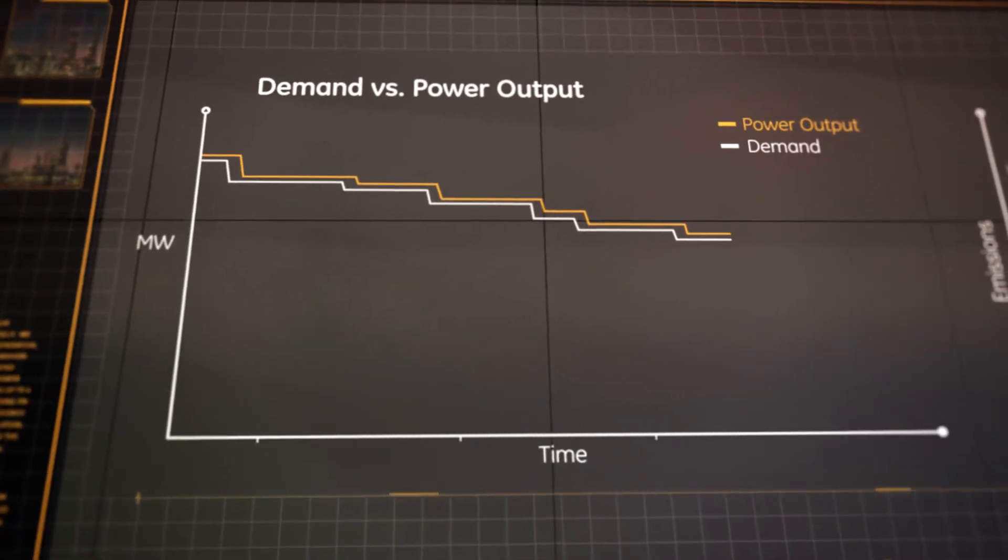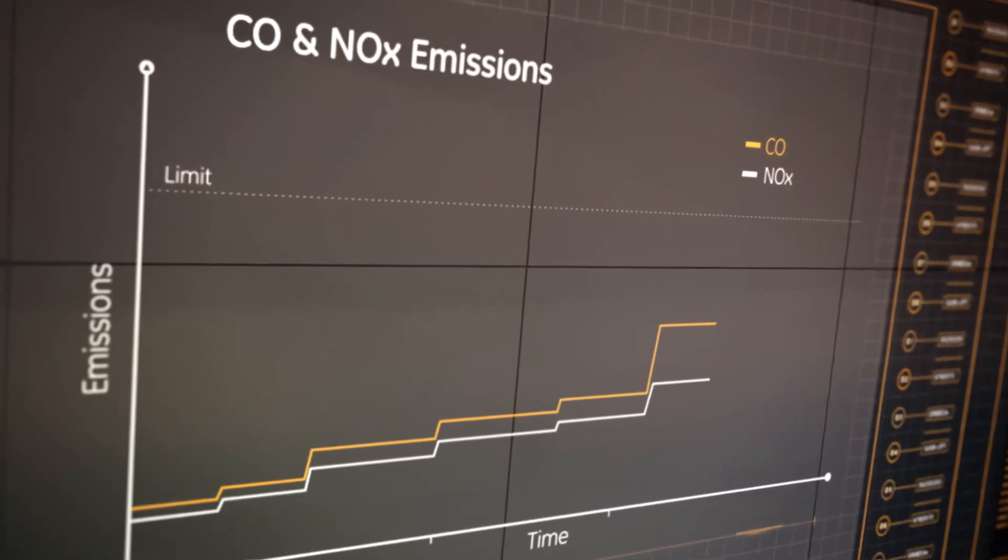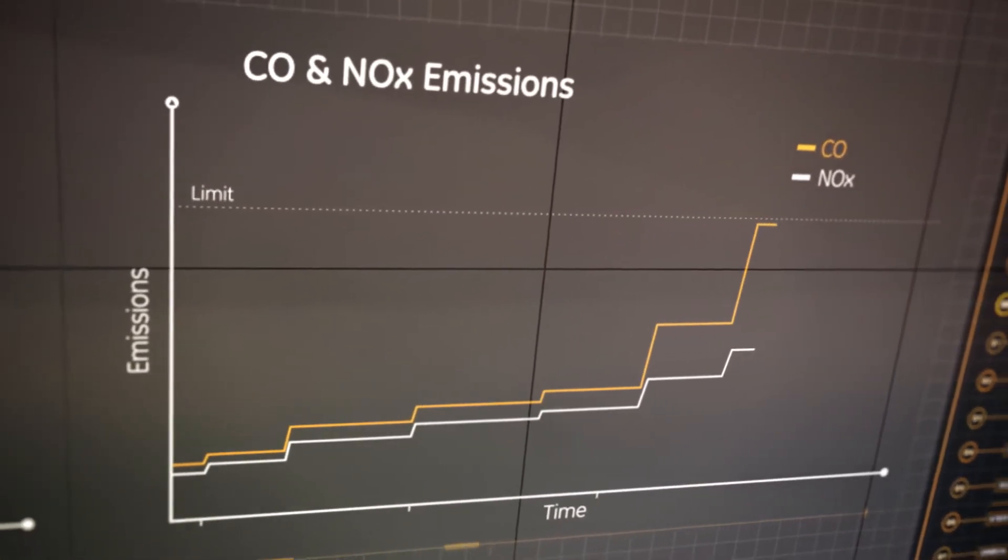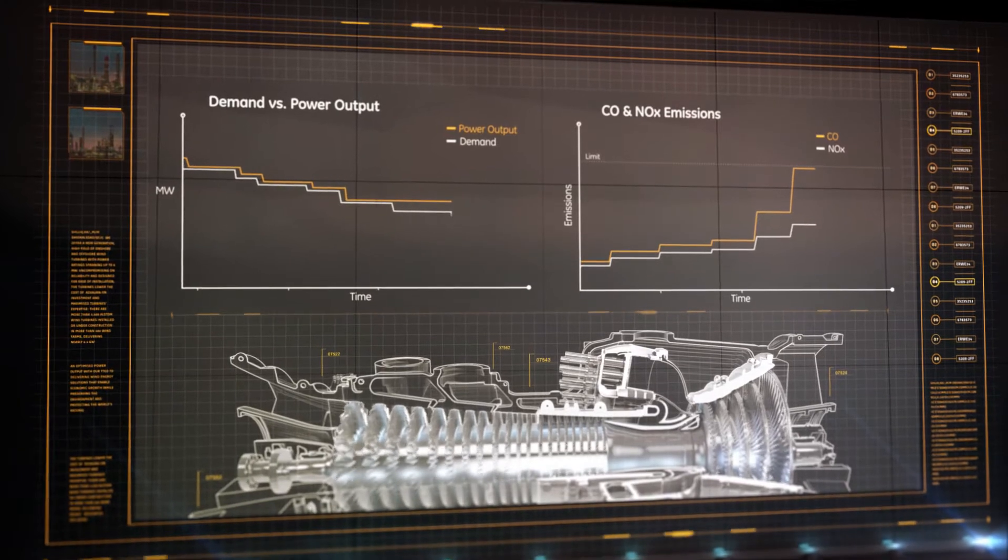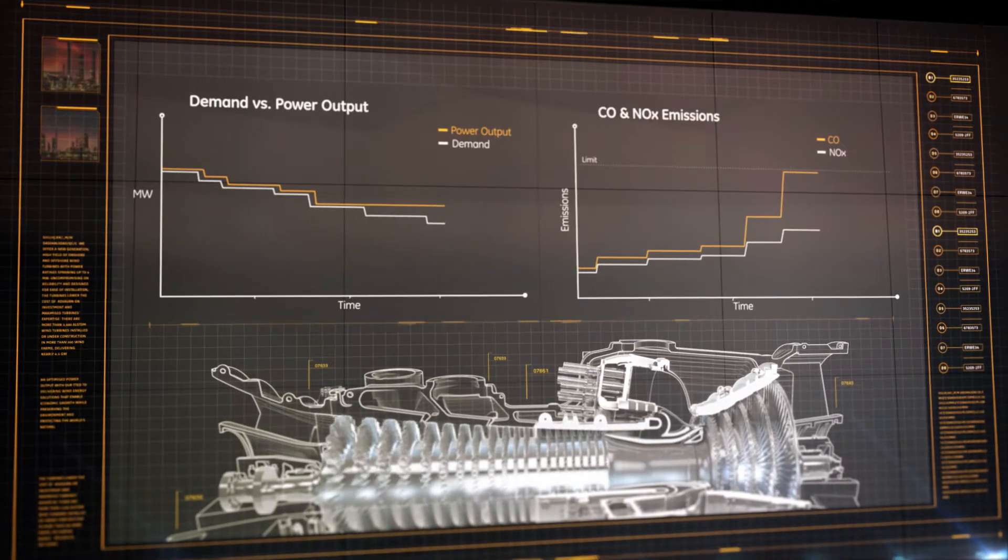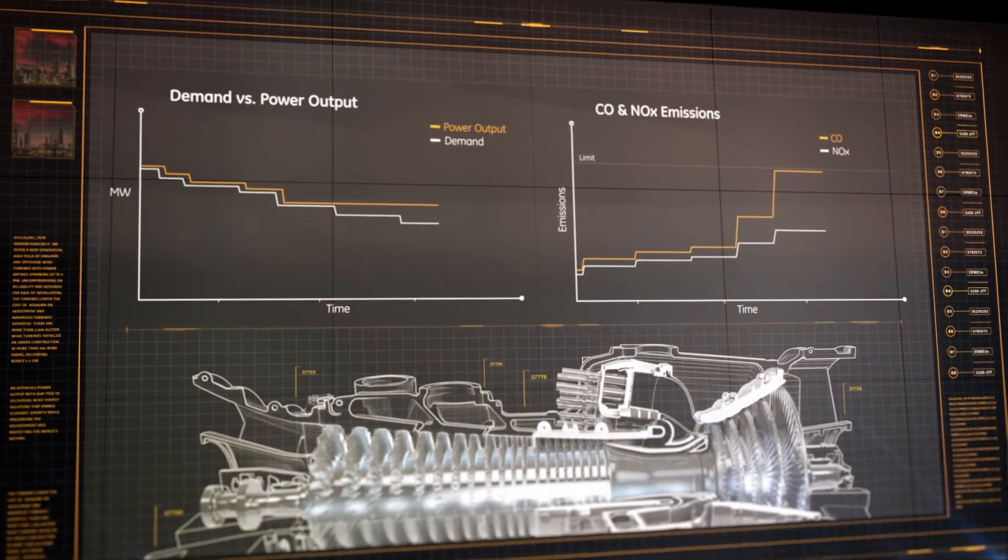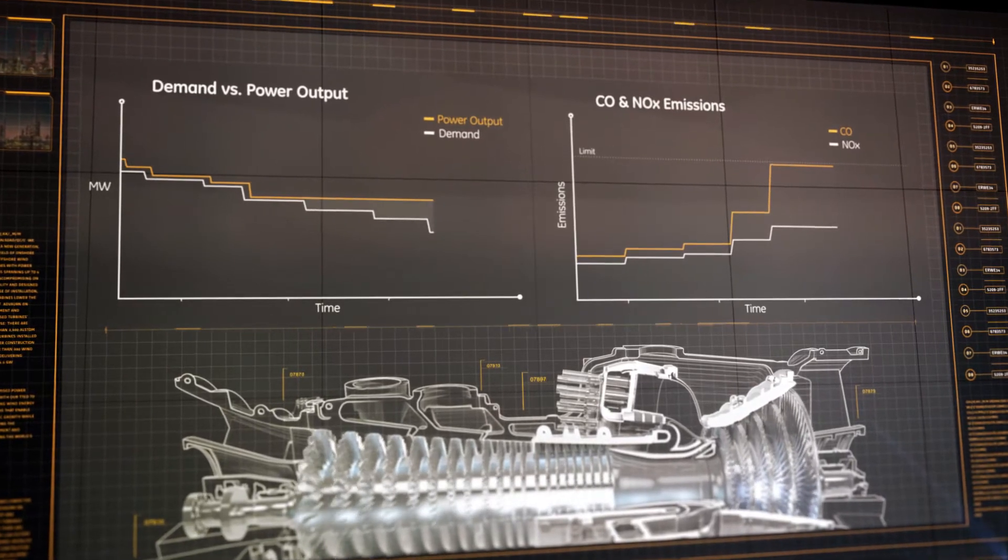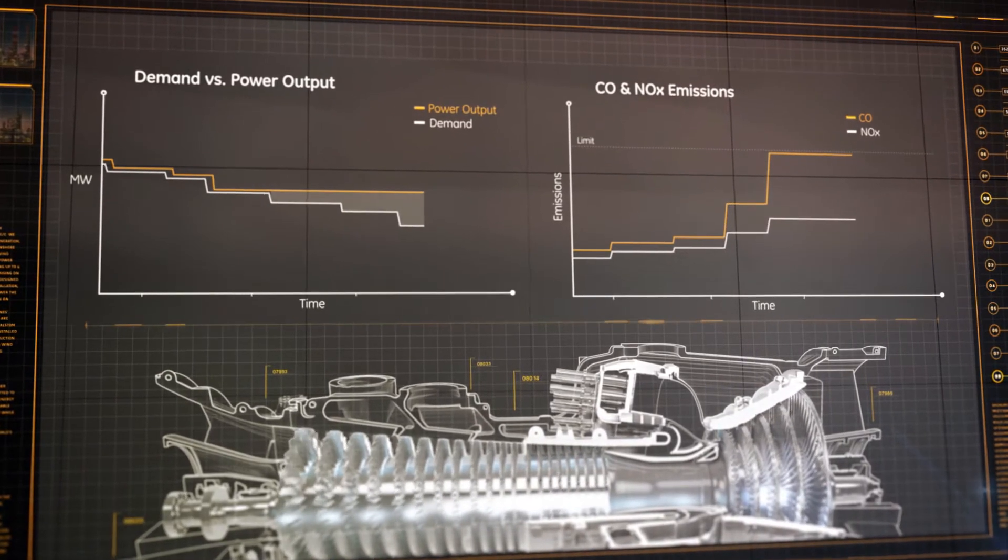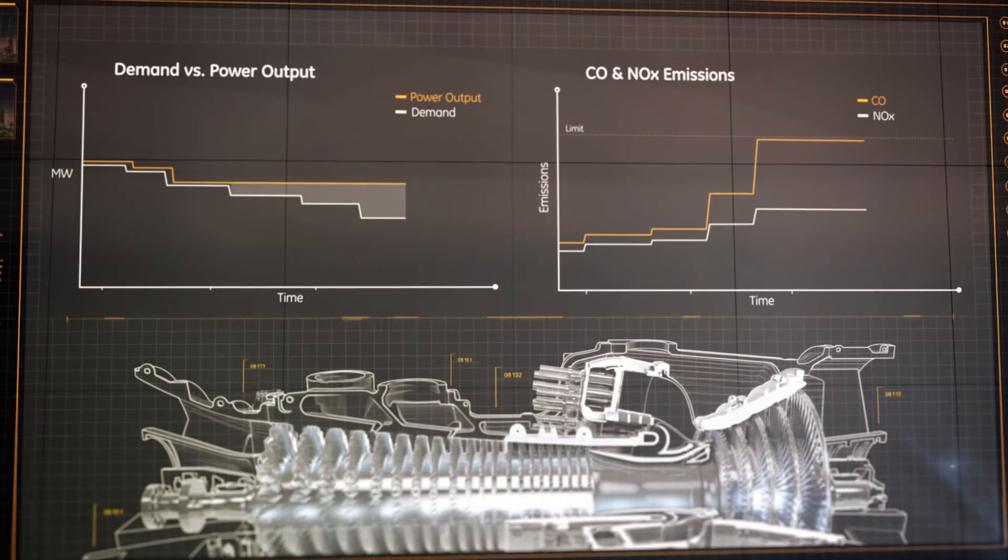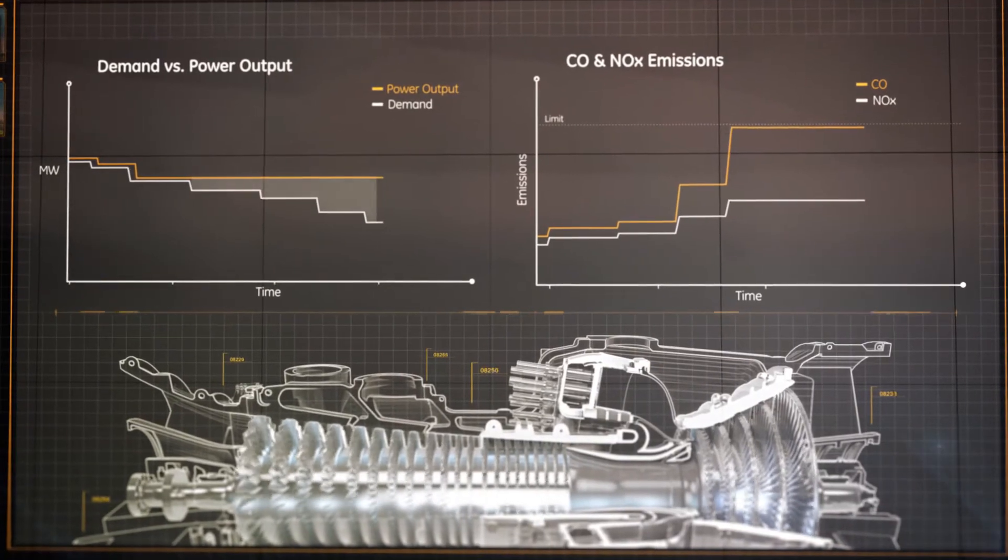As the GT load is reduced, emissions tend to increase until the environmental limit is eventually reached. Further load reduction to match the grid request may be constrained by environmental limitations. The load restriction could lead to an unbalance between the power output and the power demand. In such cases, the only option may be to shut down the GT.